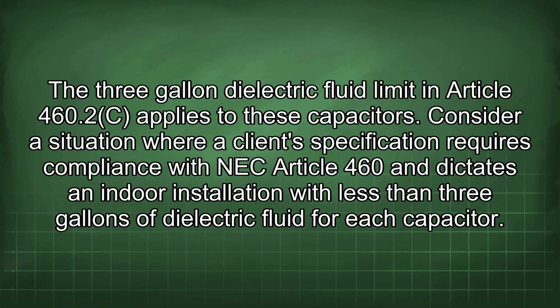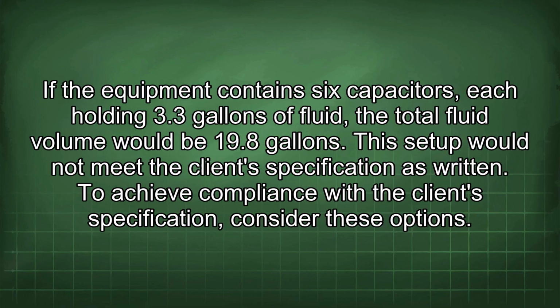Consider a situation where a client specification requires compliance with NEC Article 460 and dictates an indoor installation with less than 3 gallons of dielectric fluid for each capacitor. If the equipment contains 6 capacitors, each holding 3.3 gallons of fluid, the total fluid volume would be 19.8 gallons. This setup would not meet the client specification as written.